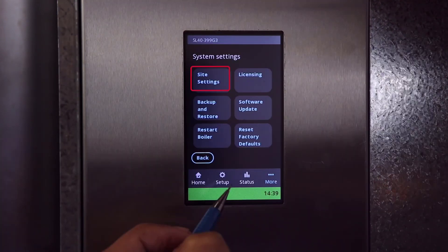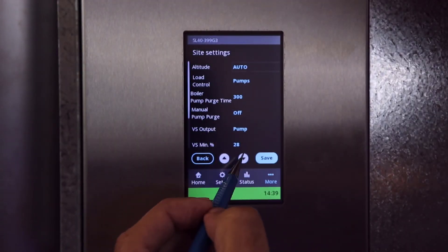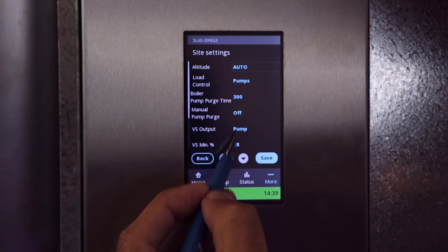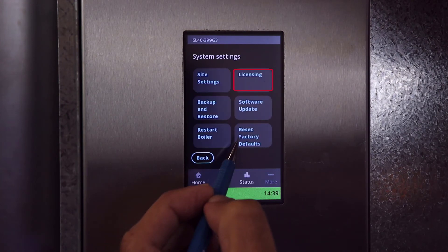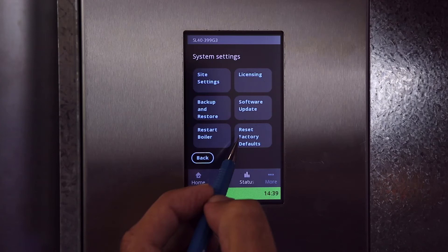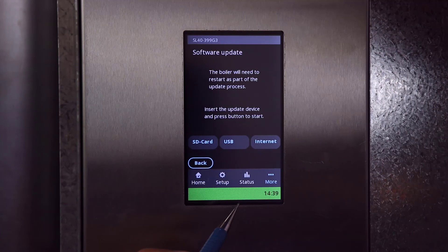System Settings is where you can find site settings, licensing, backup/restore, software update, restart boiler, and reset factory defaults. Site settings includes manual pump purge, which runs all load pumps for enabled loads — useful for purging air or testing pump operation. Another notable setting is venting material, where you can change the exhaust vent material from PVC to CPVC or polypropylene. Licensing is where you can enable BACnet if your boiler includes that option. Backup/Restore is where you can back up and restore boiler settings using a USB drive. Software update allows you to perform an update over a wired internet connection, USB drive, or SD card.